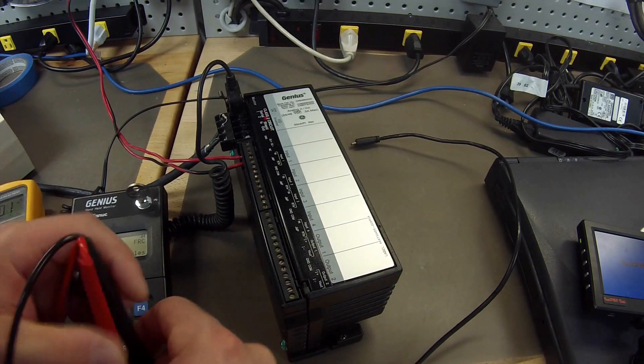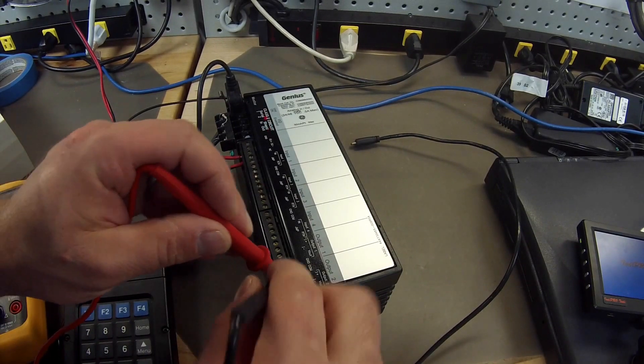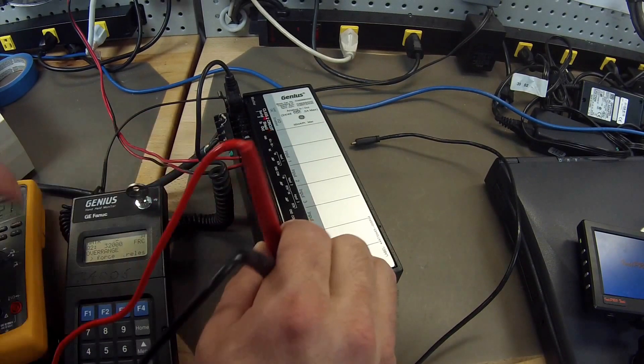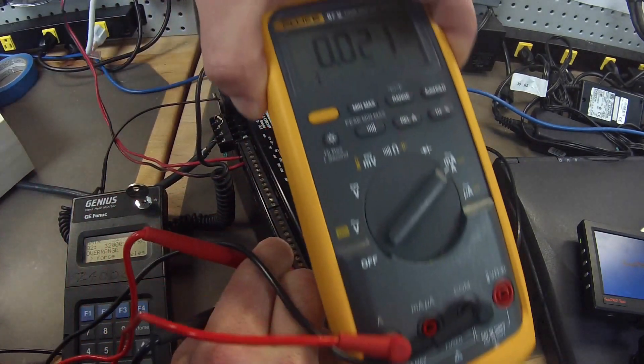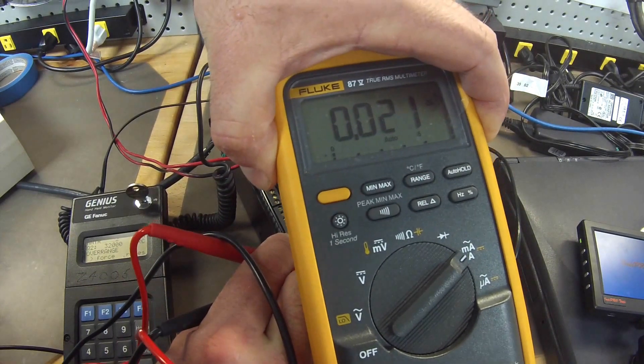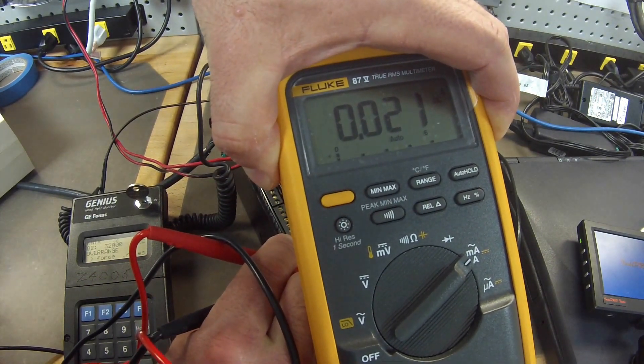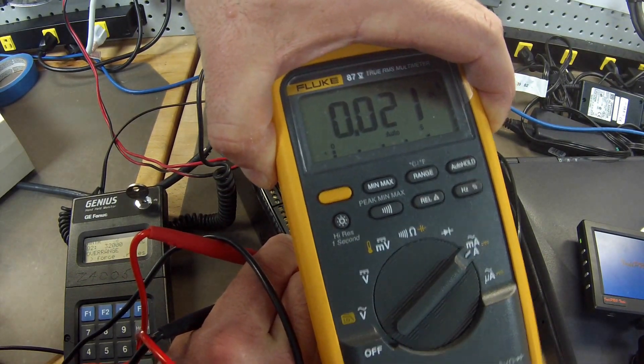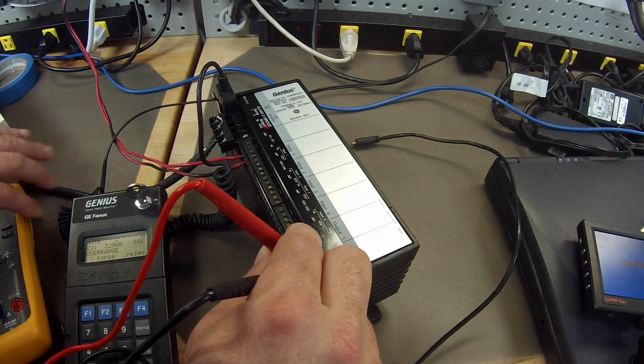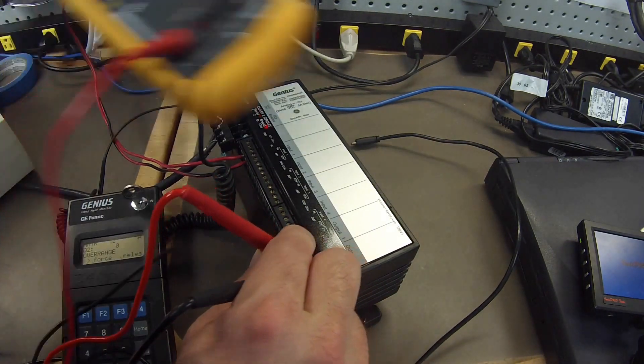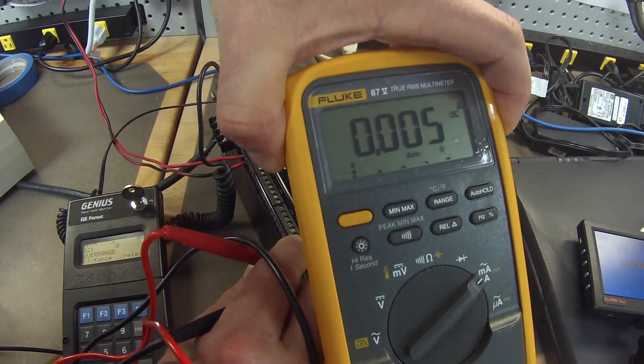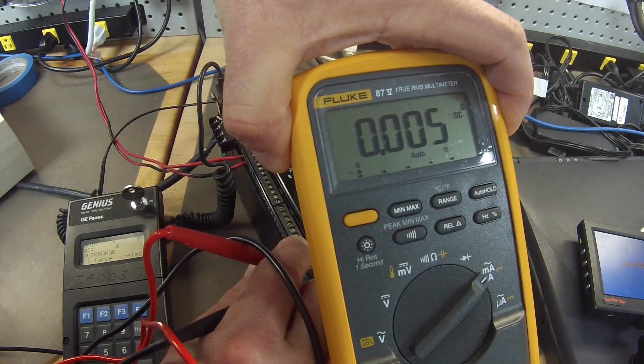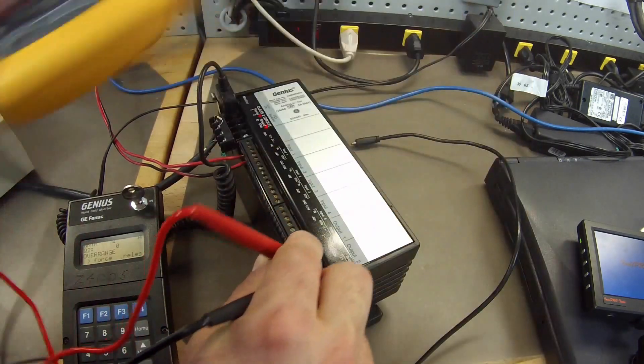We are going to go over to output number 2. Very consistent here. Very good. 21 milliamp. And I am going to release that. Make sure we can get back to that zero figure or as close to it as possible. .005. Excellent. Very consistent.